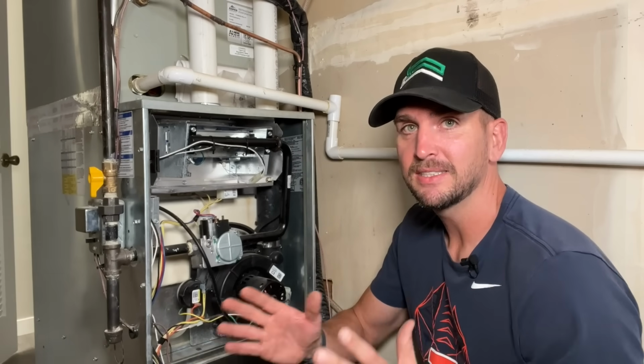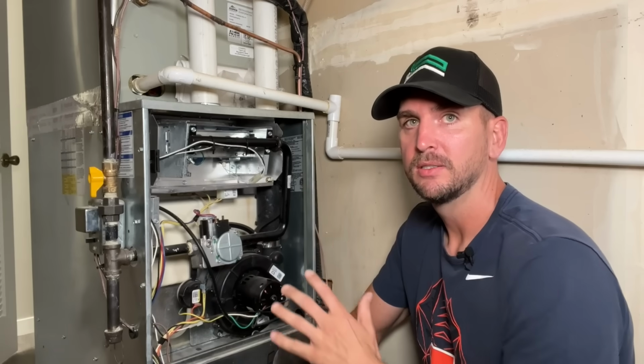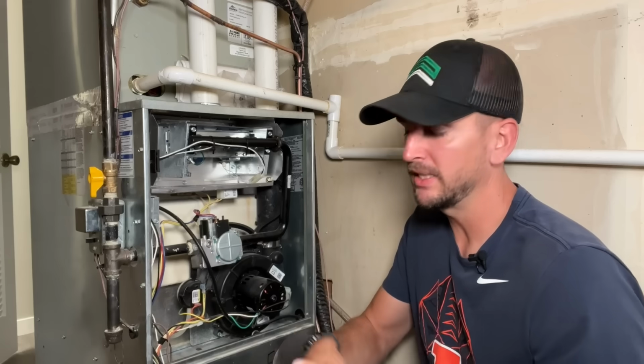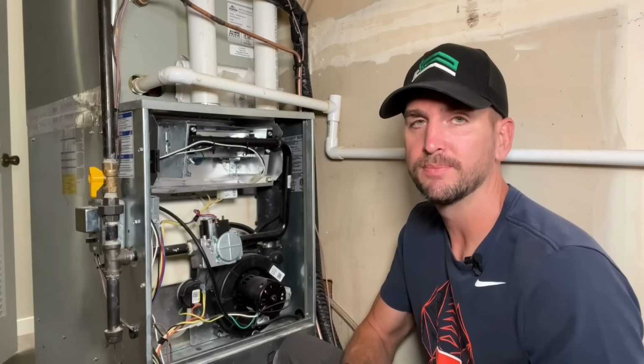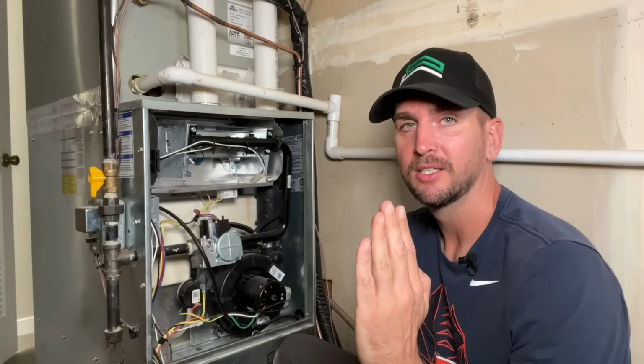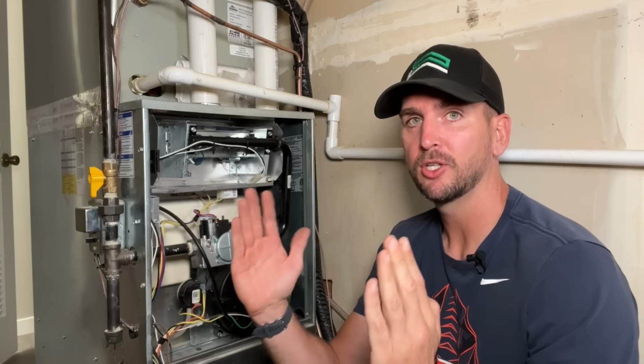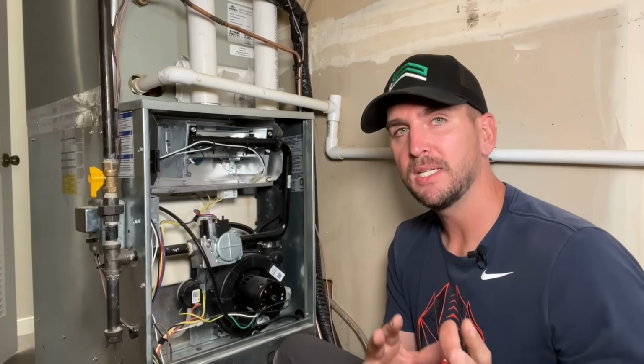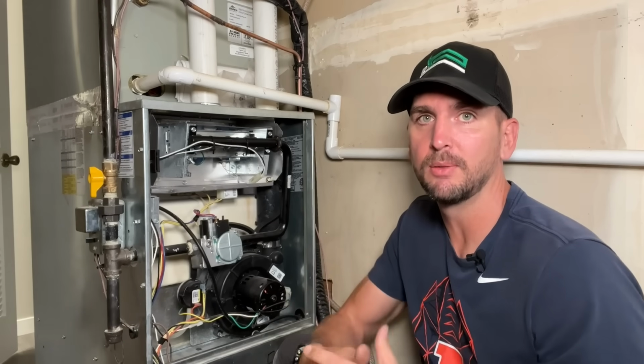Now this complete cycle for this unit takes about 1 minute and 20 seconds, and the blower fan just turned on. So between the thermostat calling for heat and the blower fan going on for this unit is 1 minute and 20 seconds, and you should be somewhere around that.